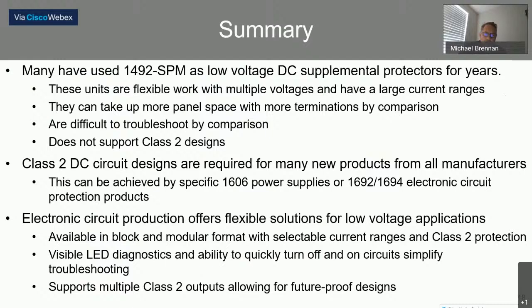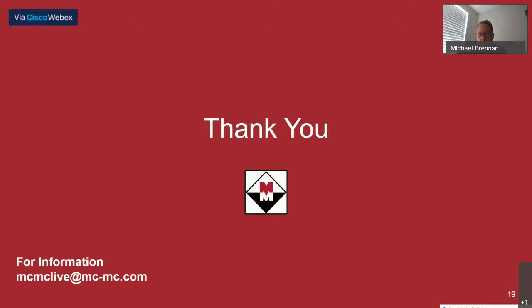The electronic circuit protection devices that we have offer a lot of flexibility because we can provide just an individual specific block with 1 input and 4 outputs, or we can supply a modular format that has 1 input, and then we can select the current ranges that are outputs or Class 2 protection that's required. We have visible LED diagnostics, and I can quickly turn on and off circuits. And again, your designs can be future-proof because more and more devices that we're seeing come out have Class 2 requirements. So, quick presentation today.